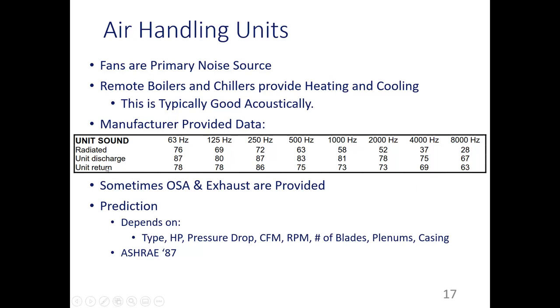So usually you have these fans, and that ASHRAE calculation I talked about for the fans is for a bare fan sound power level. Some of the better manufacturers will give you sound power in a big document of all the specifications for a particular air handling unit. It's not just meant for the acoustical engineer, but it's a critical piece of information for the acoustical engineer. And sometimes they'll have the bare fan sound power level. This might be something that you might need to do in one of your predictions.